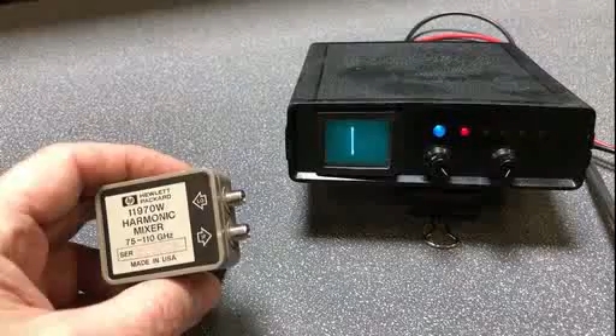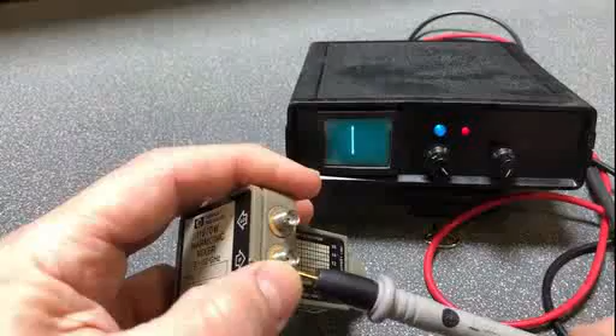The device I'm about to test is a Hewlett-Packard Keysight Agilent model 11970W harmonic mixer. This extends the spectrum analyzer series from 75 gigahertz to 110 gigahertz. It's very fast, and this is a very expensive harmonic mixer. I'm going to show how I can test the mixer diodes within this harmonic mixer.